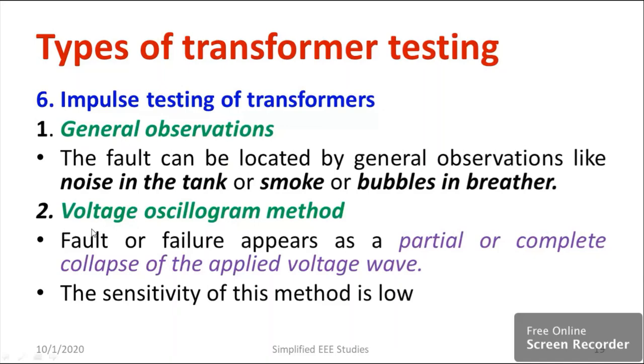This is the first observation, known as general observation. Moving on to the second procedure — voltage oscillogram method. This is done by measuring the voltage waveform shape. A fault or failure appears as a partial or complete collapse of the applied voltage waveform. You compare the input and output waveforms — input from the impulse generator, output from across the transformer winding — and if there is a failure, a sudden voltage drop will occur. However, the sensitivity and accuracy of this method is somewhat poor.